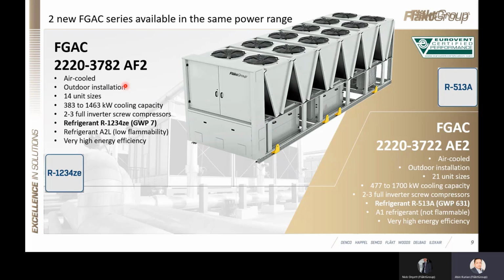This refrigerant is classified as A2L, which is slightly flammable. The thermodynamic property of this refrigerant is not as good as R134A or R513A. Because of that, we need to use a bigger frame for the chiller and bigger compressors. This will make the chiller 15 to 20% more expensive than a standard R513A or R134A chiller.